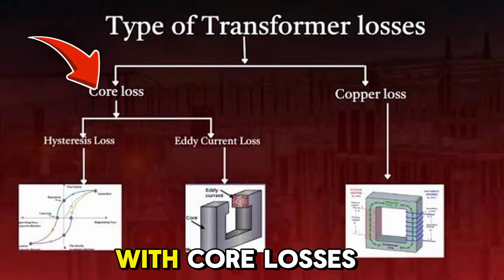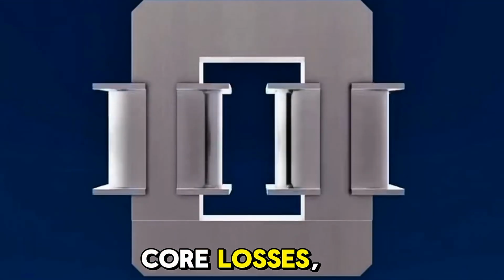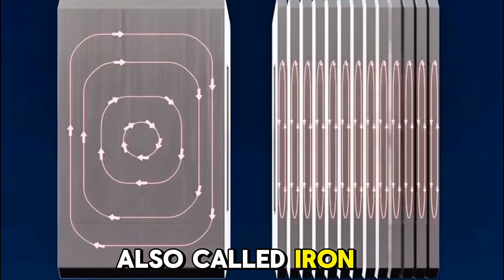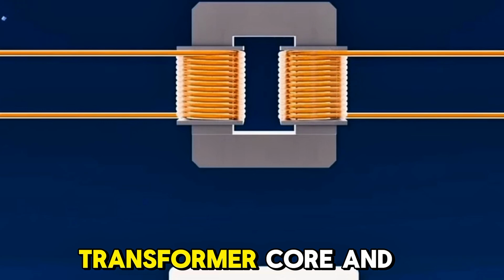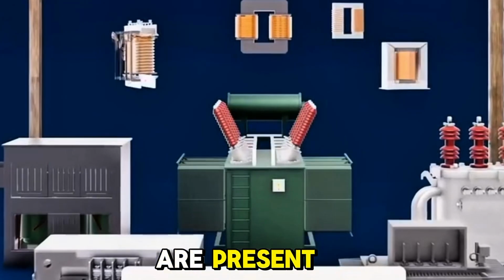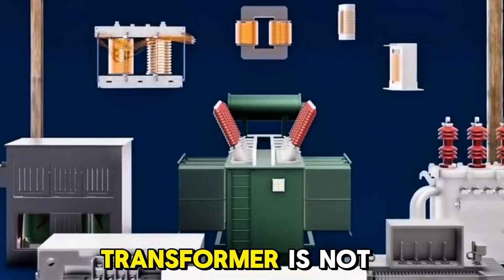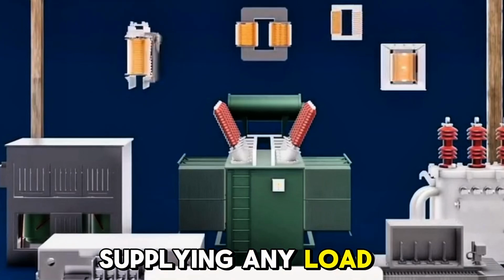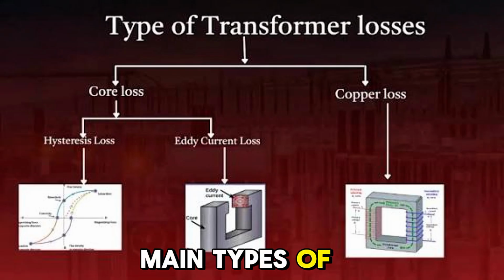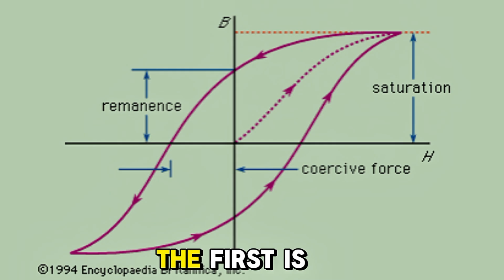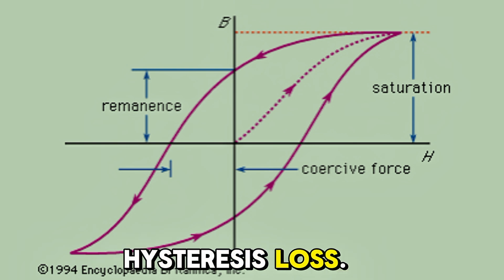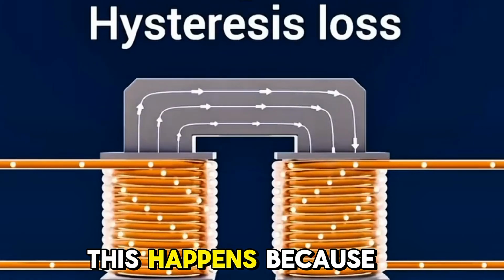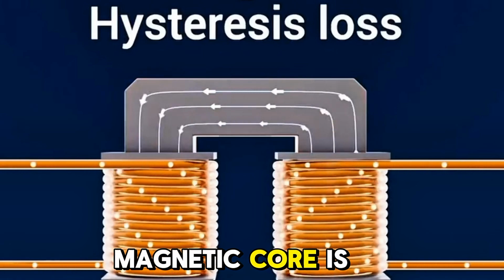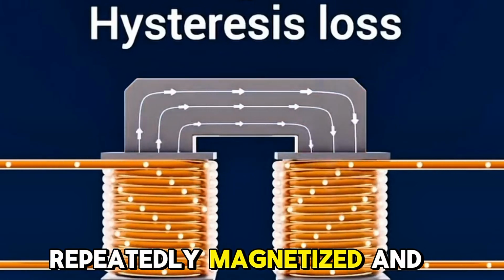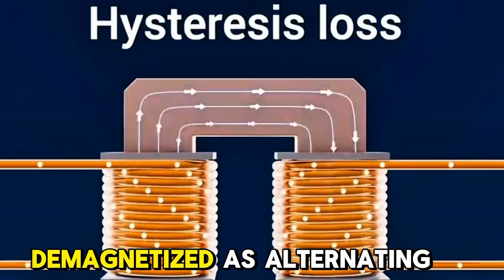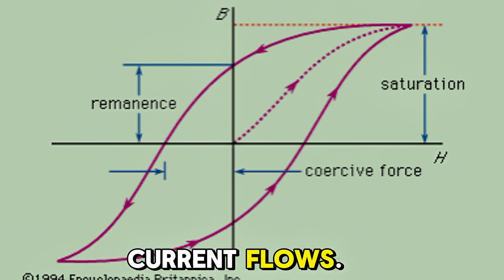Let us start with core losses. Core losses, also called iron losses, occur in the transformer core and are present even when the transformer is not supplying any load. There are two main types of core losses. The first is hysteresis loss. This happens because the magnetic core is repeatedly magnetized and demagnetized as alternating current flows.